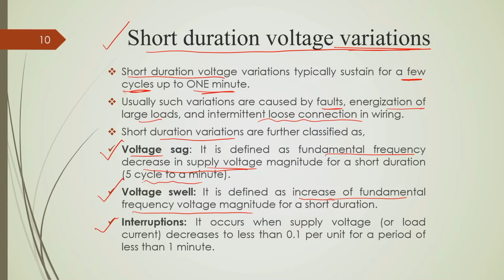And interruption means when supply voltage becomes 0 or as low as 0.1 per unit, that means 10% of the nominal voltage, and lasts for less than 1 minute; it is called short duration interruption. Okay. So, if I draw voltage sag, it is something like this. Suppose this is your fundamental frequency voltage. The frequency remains the same, but it dips in magnitude for a few cycles like this, and that causes voltage sag. This is the voltage waveform with respect to time.